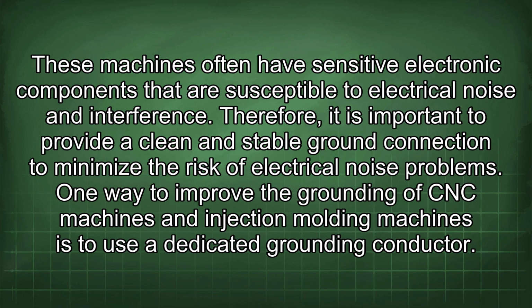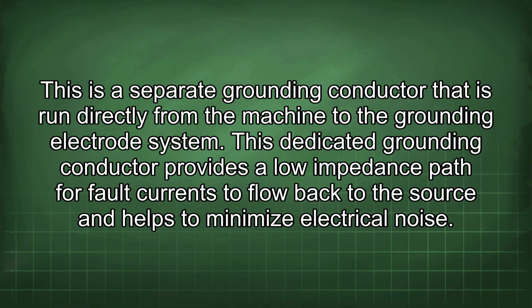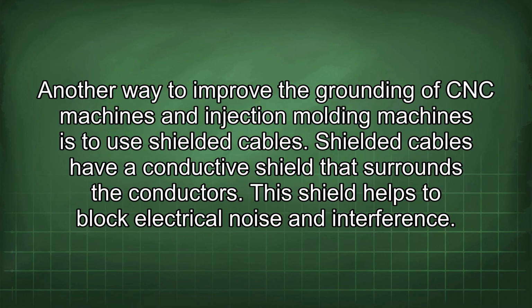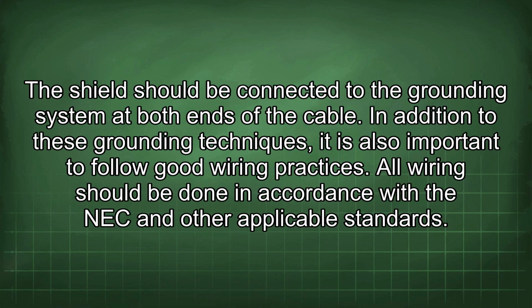One way to improve the grounding of CNC machines and injection molding machines is to use a dedicated grounding conductor. This is a separate grounding conductor that is run directly from the machine to the grounding electrode system. This dedicated grounding conductor provides a low impedance path for fault currents to flow back to the source and helps to minimize electrical noise. Another way to improve the grounding of CNC machines and injection molding machines is to use shielded cables. Shielded cables have a conductive shield that surrounds the conductors. This shield helps to block electrical noise and interference. The shield should be connected to the grounding system at both ends of the cable.